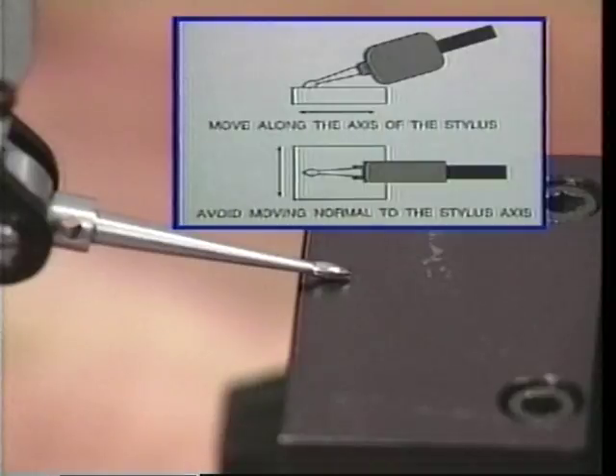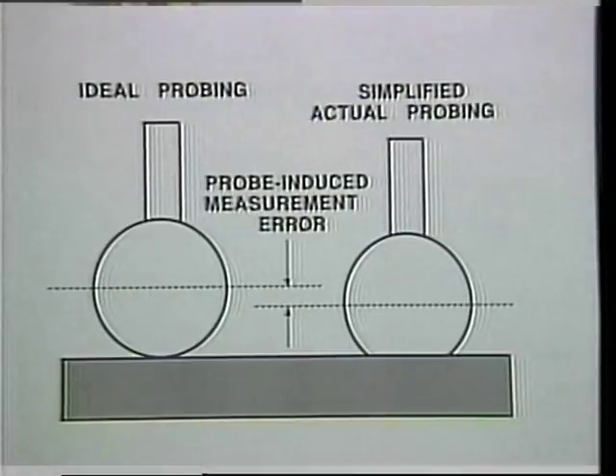Although this is a contacting measurement device, the gauging force for this stylus is less than 0.2 ounces, a force which may be acceptable for many applications. Other measurements might be undermined by the deformations resulting from these small contact forces. While these forces are very small, the contact areas are even smaller. Therefore, the contact pressure becomes sufficient to produce measurable distortion of both the specimen and the stylus. These distortions obscure the true dimension, especially if the contact force varies over the course of the measurement.